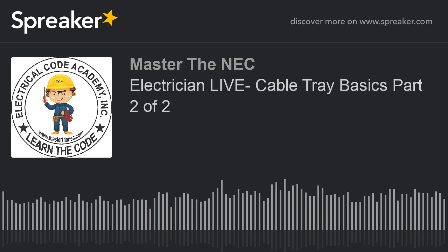So basically it's saying, look, if the cables that I'm putting in this tray don't have more than 3 current-carrying conductors, then I'm good. I'm pulling the ampacities from 310.16, and I'm not going to have to do anything. That's what it's starting to say. Now, it also reminds you, because you're thinking, well, Paul, don't I have a bunch of conductors in this tray? Just relax. We're not there yet. Then it says the adjustment factors shall be limited to the number of current-carrying conductors in the cable and not the number of conductors in the cable tray. That's a beautiful thing, right? Because basically what that's saying to me is that, you know what?